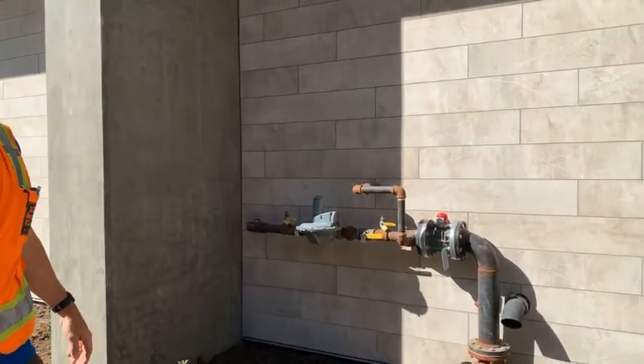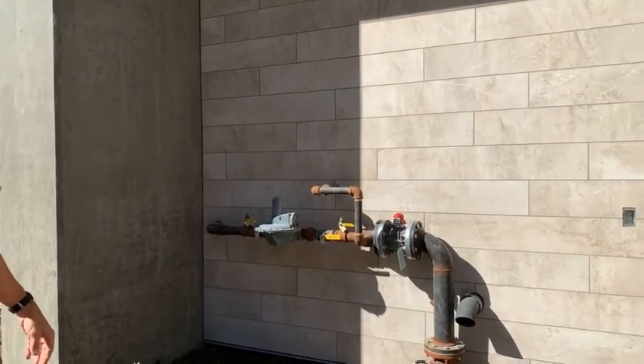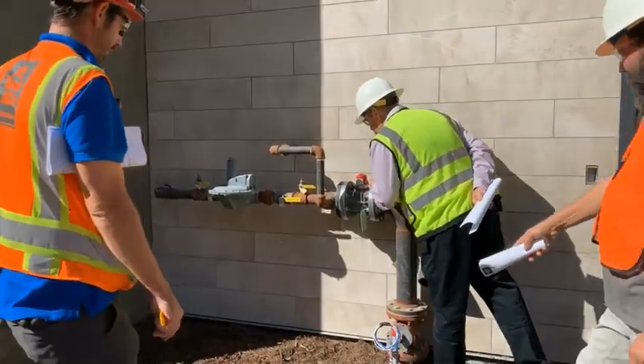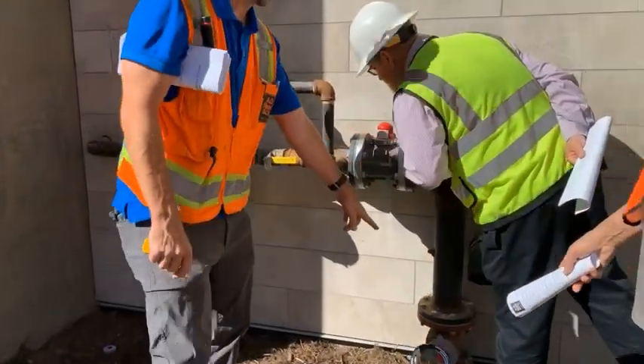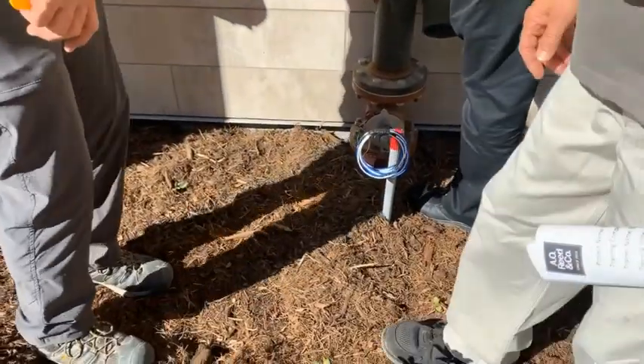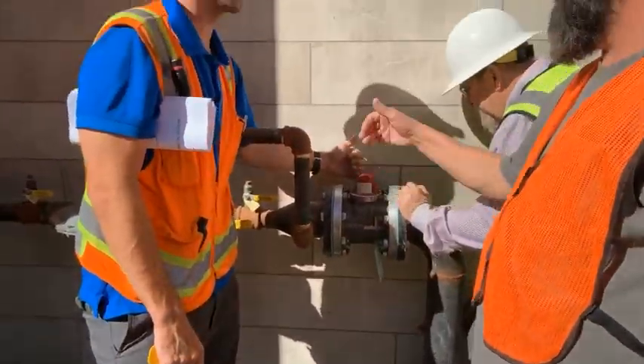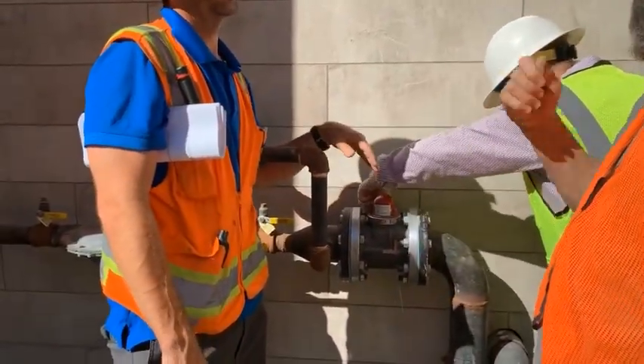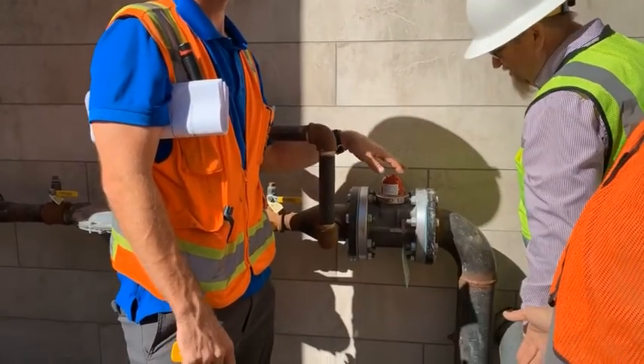Those earthquake valves. You mentioned when you reset it, you shut the main off first. Yeah, shut the main off. Sometimes you can reset it, like this one's going to be hard. I have done some small ones where I've just gone over and hit it with the screwdriver at an angle, and it resets without shutting the gas off. That's what I'm saying.